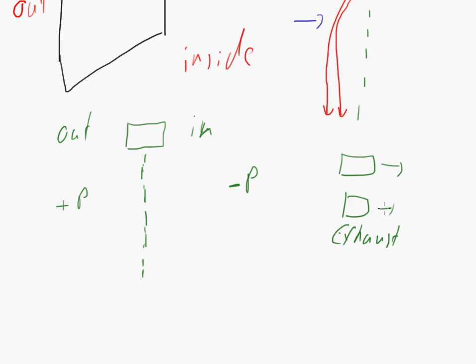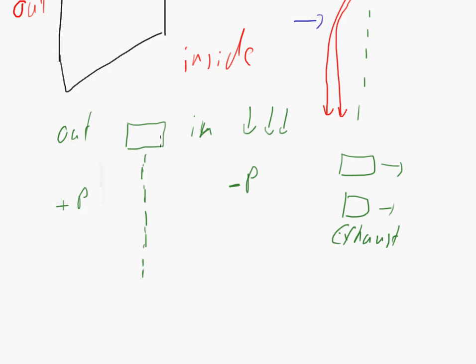And those exhaust fans push that air out. And you have maybe not so many fans, or your air supply is not as much as the air exhausted. So you have here sometimes less pressure than the pressure outside. And what happens here with the air curtain - when you have this pressure differential, air from the outside will have a much easier time coming into the building.